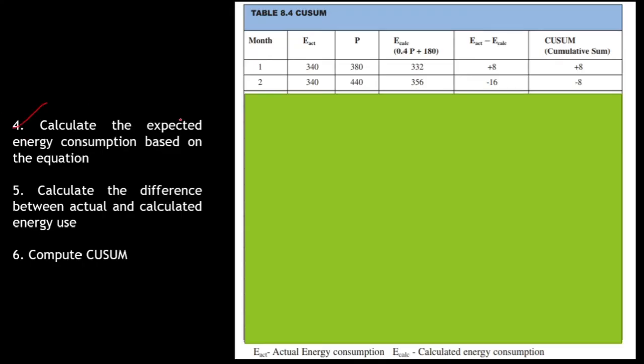Step 4: calculate the expected energy consumption based on the equation. The equation is E = 0.4P + 180. For the first data point, P = 380, so E_calculated = 0.4 × 380 + 180 = 332. You simply substitute each production value into this equation to generate the calculated energy column.